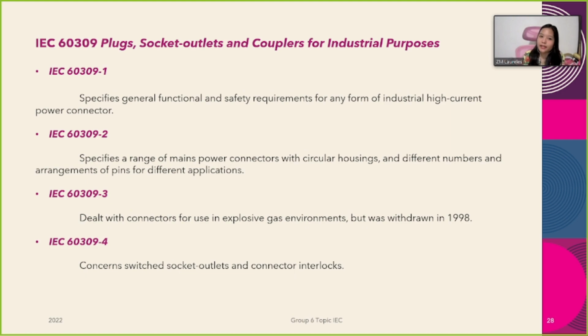Then we have the IEC 60309, which is of course an international standard from the IEC for plugs, socket outlets, and couplers for industrial purposes. So meron tayong highest requirement in terms of voltage which is allowed by the standard na 690 volts DC or AC. Para naman sa highest current is 250 amperes. Highest frequency is 500 Hz and yung temperature range niya is between negative 25 degrees Celsius to 40 degrees Celsius.